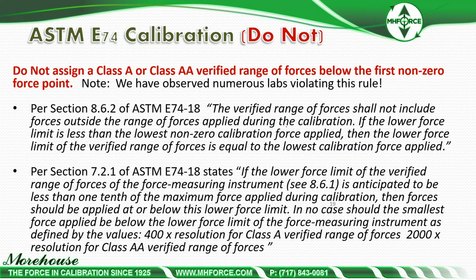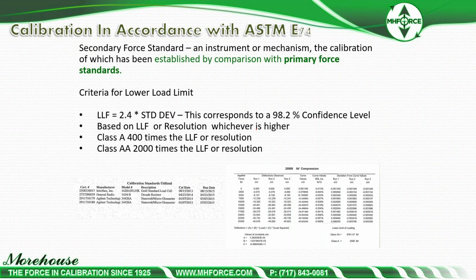8.6.2: the verified range of forces shall not include forces outside the range of forces applied during calibration. Look, we've read this. Here it is. It's clear. Labs that are doing this are in violation of the standard. Just wise up. If you have a cert that says your lower limit is less than the first non-zero test point, that cert is incorrect. Secondary, for calibration in accordance with the E74 secondary force standard. This is the one that, remember, has been established by comparison with primary standards. Lower limit.